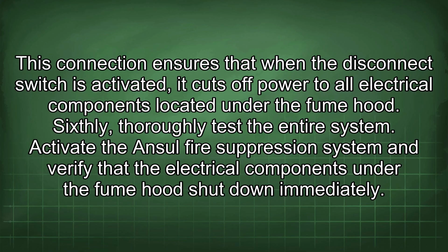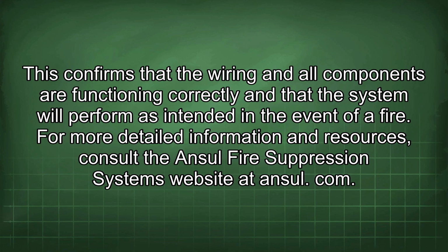Sixthly, thoroughly test the entire system. Activate the Ansul fire suppression system and verify that the electrical components under the fume hood shut down immediately. This confirms that the wiring and all components are functioning correctly and that the system will perform as intended in the event of a fire.